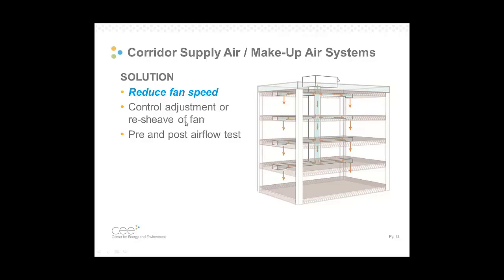Supply systems or makeup air systems. The solution here, if you're measuring and determining that they're bringing in excessive outdoor air, is simple. It's reducing the fan speed. This can be done with a control adjustment in the simplest case, or a resheave of the fan, which is a way of saying they're changing out the pulleys for reduced fan RPM. And then, of course, there's a pre and post airflow test to verify or to document the energy savings. This is standard work for a test and balance contractor, and usually ends up being done in a day.